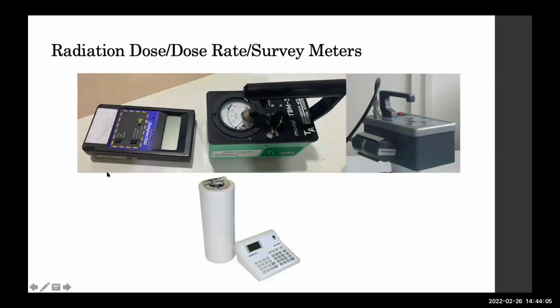Now, there are many survey meters and contamination monitors which are used for radiation safety purposes in nuclear medicine. They are GM counter based or ion chamber based. You are very familiar with these instruments, which are routinely used for checking the contamination and dose rates. Now, this is the dose calibrator. This is also an ion chamber based apparatus. Like any medicine which we give to the patient, it should be measured and it should be given in the right optimal amount. So is the case with the radioactivity.